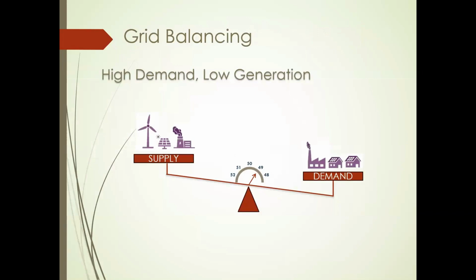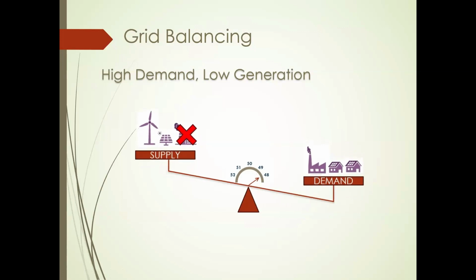From the point of view of the grid also, this confirms it. Now you can see that this is an under frequency situation. I see here frequency is lower, high demand, low generation. If you try to take the unit into house load mode, you will take out this generation, making the supply side lighter, going further into low generation, so that ultimately the grid will lose its valuable generation, and the system will slide down to failure, an imminent blackout during the under frequency.